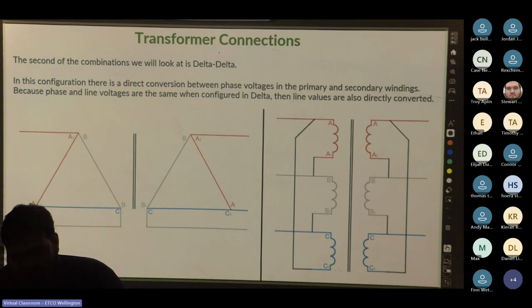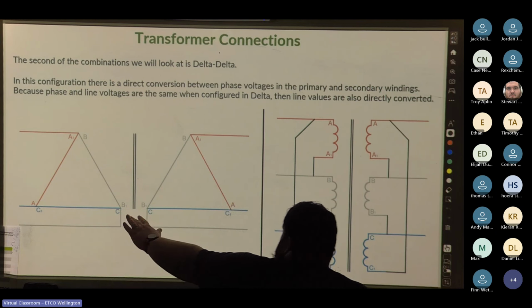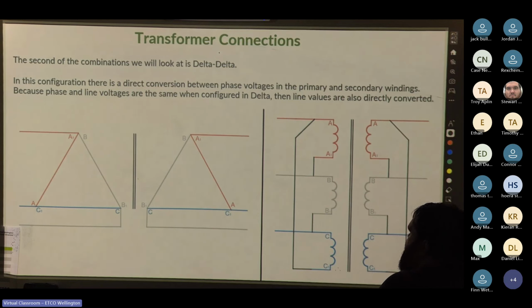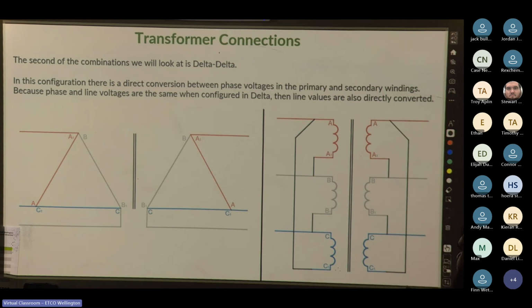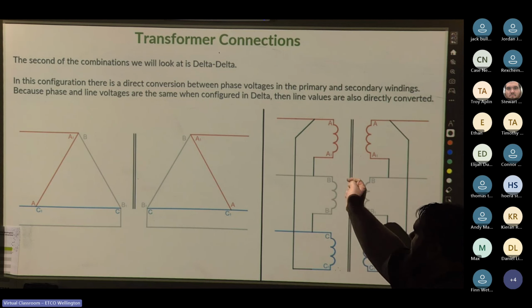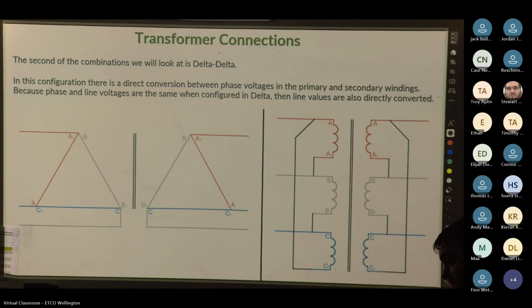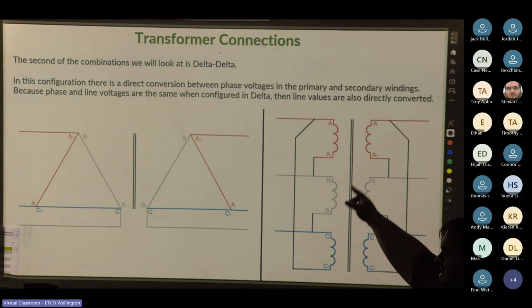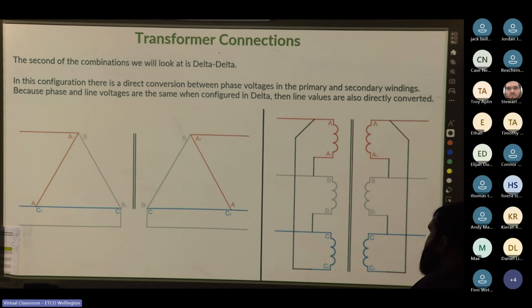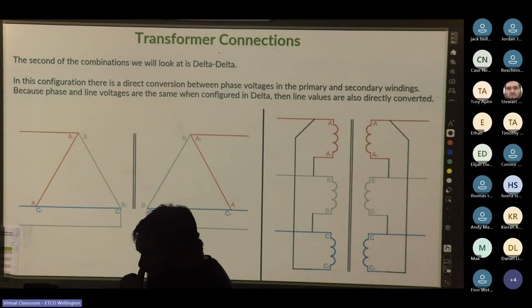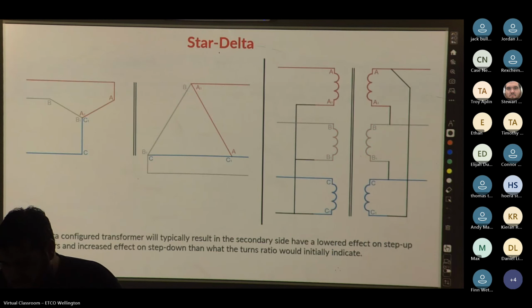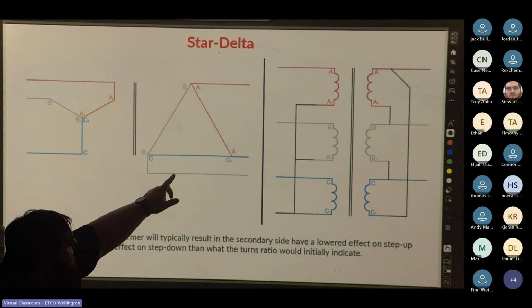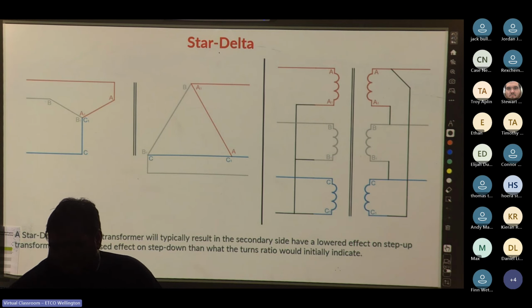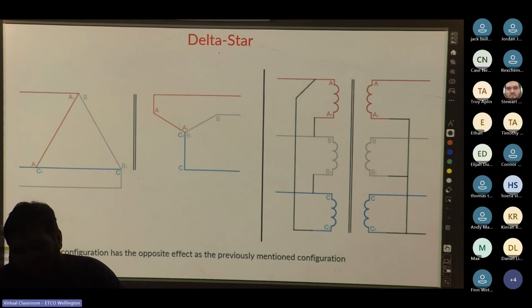And this is a delta. So on the left, we've got the symbol of the triangle. And on the right, we've got how it would physically be wired up. So you can see we've got a tap off each winding, but all the windings are connected together in a series loop with taps off at each point. So that is our delta connection. And then, as the network guys will know, this would be star delta. So you see on the left, we have a common neutral point, and on the right, we have series windings connected together. Delta star is just the opposite.